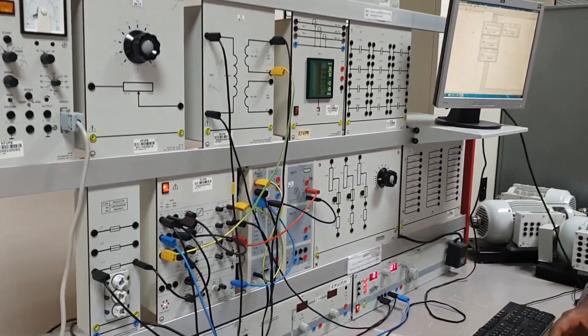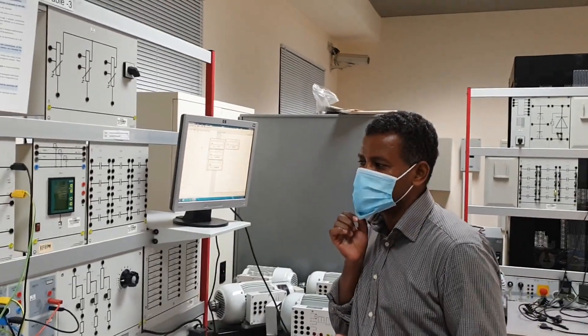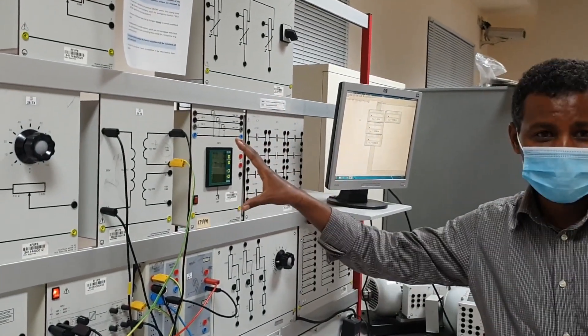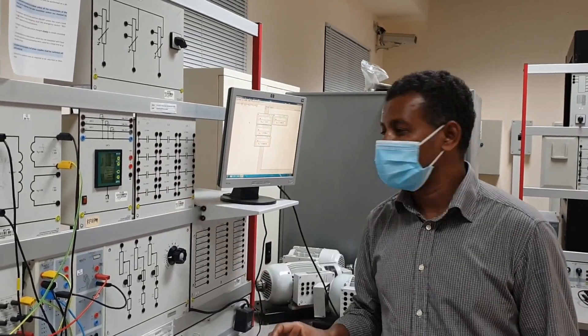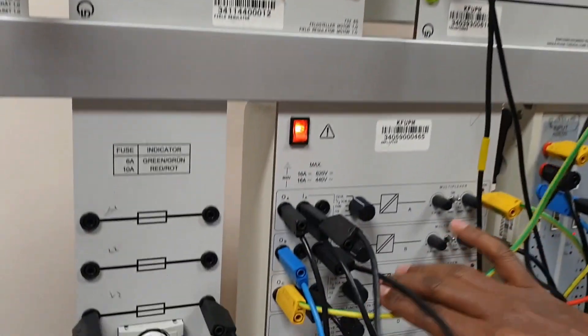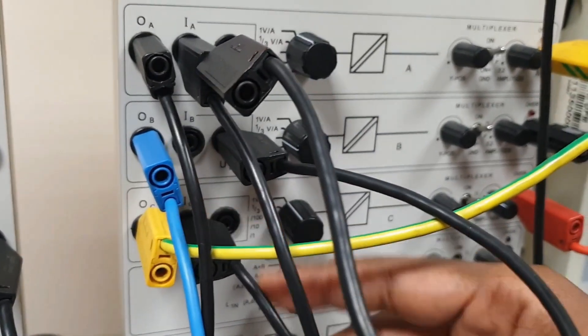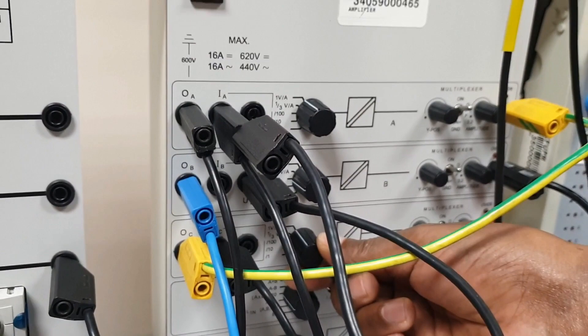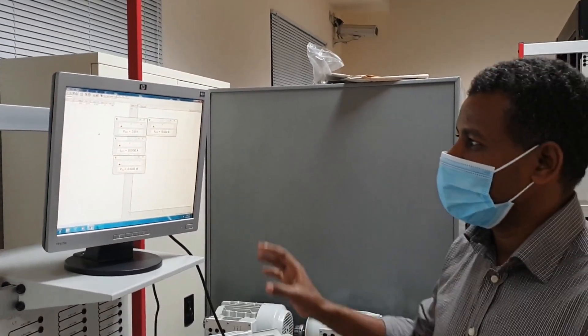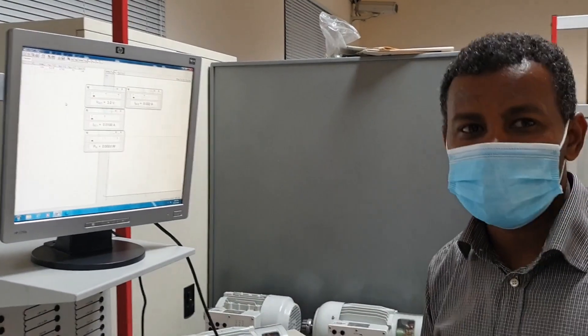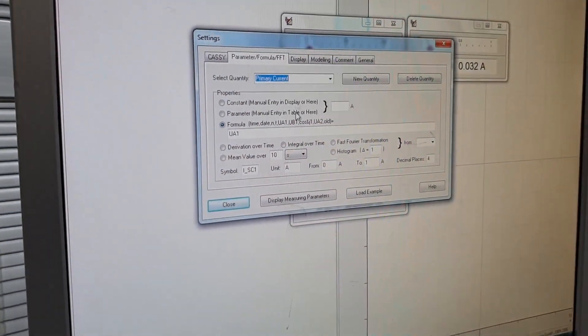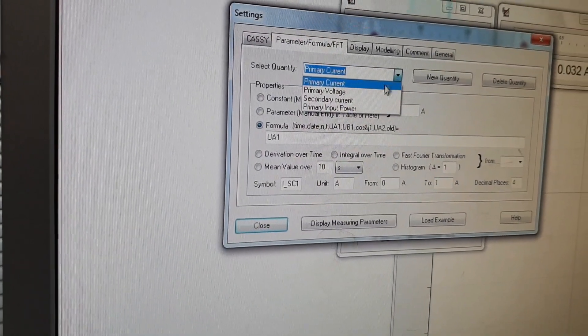This is part two — the short circuit test of the transformer. For open circuit test we apply rated voltage; for short circuit test we apply rated current. It's like testing the equipment under no load and under full load. In the short circuit test, when you short the circuit, the current will be extremely high, so we must conduct a systematic short circuit test. The secondary winding was previously open — now we have shorted it and connected an ammeter to measure the secondary current. We have also defined new quantities in CASSY: Isc for the short circuit test, to differentiate from the open circuit test quantities.